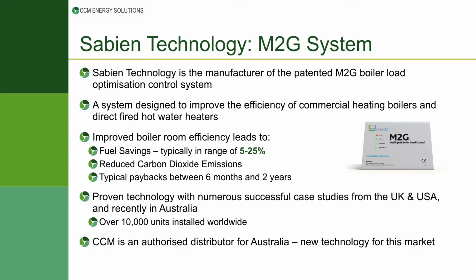For small commercial boilers from 100 kilowatts up to 2 megawatts, we look at a completely different technology, manufactured by Sabien Technology, and they have a patent on their M2G system. It is designed to stop the inherent problem of dry cycling. Small boilers typically have high-low burners or on-off burners, and they will turn on and off repetitively, maybe 15, 20, 30 times an hour. This system is designed to stop that problem.